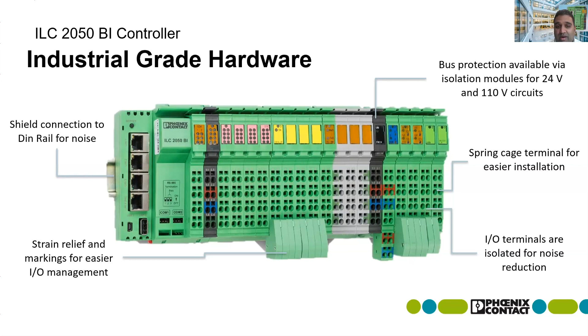This is a range of I/O modules that are connected on an ILC controller. But equally, in terms of designs, we also have remote I/O solutions. Some of the advantages this provides are being able to collect and control I/O signals with a distributed approach. We also take Niagara here, and we've developed a driver specific for Niagara that allows you to easily discover your remote I/O. Any modules connected on your remote bus, you can scan that on the bus, and it responds with how many modules it has, and then it automatically creates your I/O points in your design. So when an engineer goes to program the points, he's already got access to them.